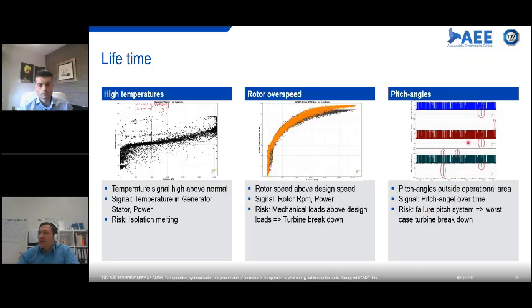This last example on lifetime I want to show you is how we can see on a time series if my pitch is not doing well. As you can see here, we have from one turbine the three phases operating of a pitch. We know by definition that the pitch of a turbine runs between almost 0 degrees up to 90 degrees, so if we're slightly above or below, it's not an issue. But as you can see here over time, the turbine was going way above or way below this level, and this could be a problem. Depending on the construction of your turbines, it could have already caused a breakdown in one of your components.